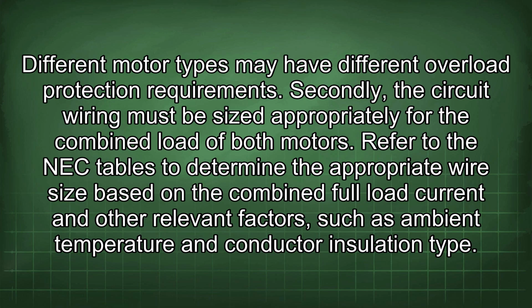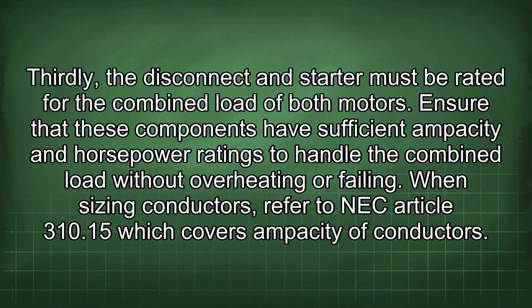Secondly, the circuit wiring must be sized appropriately for the combined load of both motors. Refer to the NEC tables to determine the appropriate wire size based on the combined full load current and other relevant factors such as ambient temperature and conductor insulation type. Thirdly, the disconnect and starter must be rated for the combined load of both motors. Ensure that these components have sufficient ampacity and horsepower ratings to handle the combined load without overheating or failing.